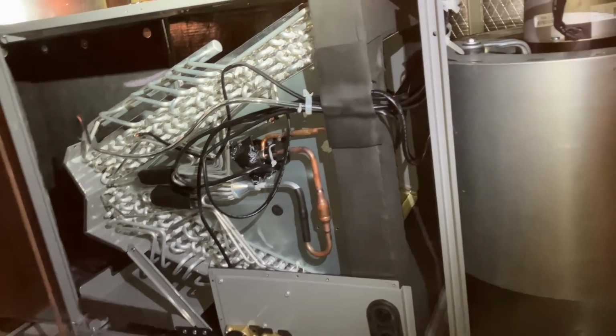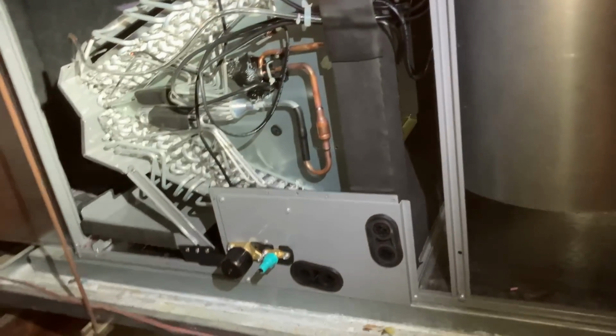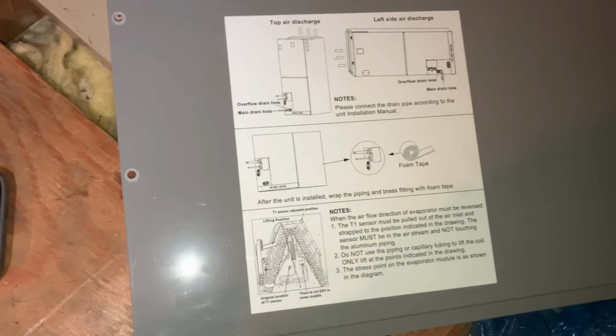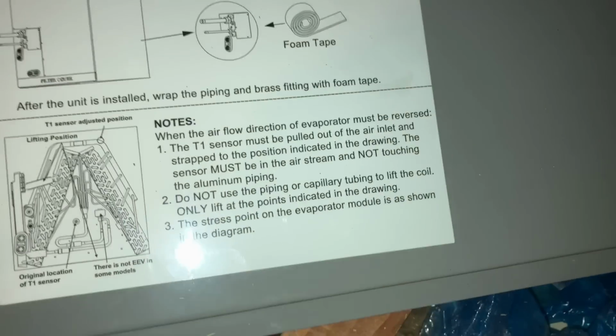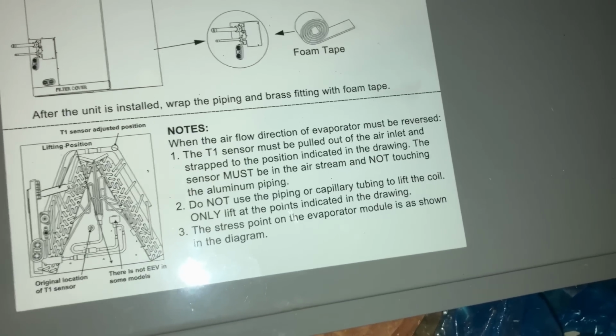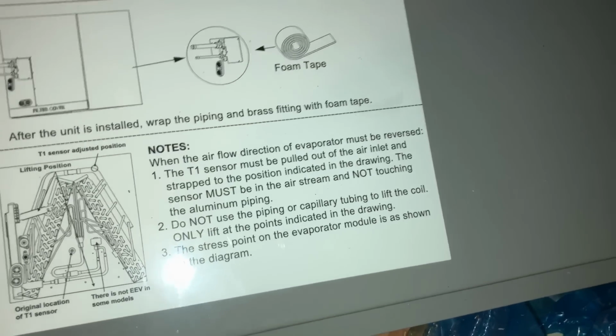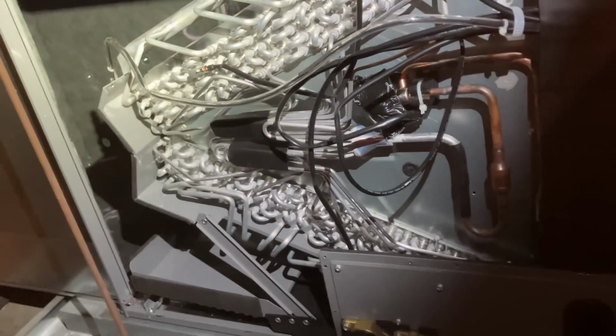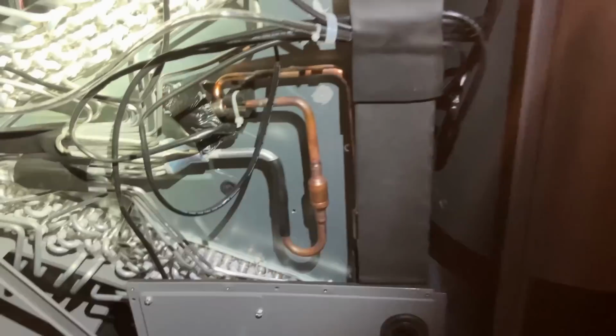A few minutes after 11 here. Our air handler is in position. We reversed the evaporator, and I button everything up. I was reading that sticker there, and it says when you change the direction of the airflow, the T1 sensor must be changed. Now this T1 sensor was inside that little rubber grommet hole, and that would have been the airflow coming in this way when it was discharging out the left. Now it's coming in from the left and going out the right. So that sensor is sensing that air temperature before it hits the evaporator. So we moved it there as indicated in the factory instructions. And now we're going to button all this back up together.